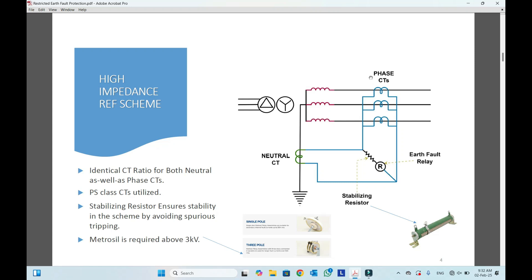Now for the balanced condition, for example when three-phase current is running — say 100 amperes in red phase and 100 in blue phase — the summation would be zero because there is balanced current. When there is balanced current, meaning zero, and there is no earth fault condition and no current flowing through the neutral, this relay — R is our restricted earth fault relay — will be stable.